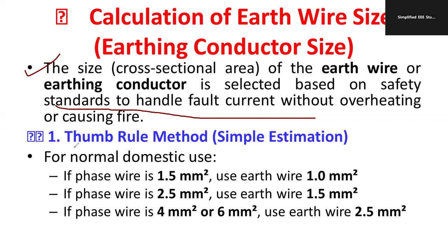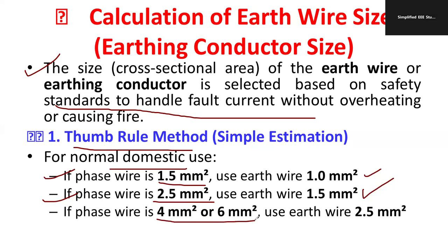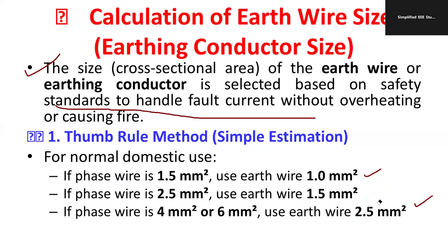For general installation, we follow this thumb rule: for normal domestic use, if the phase wire is 1.5 mm², the earth wire should be 1.0 mm². If the phase wire is 2.5 mm² — for heavy load applications — the earth wire should be 1.5 mm². For motors or extra heavy loads, use an earth wire of 2.5 mm². Contractors commonly apply this chart based on experience during installation.